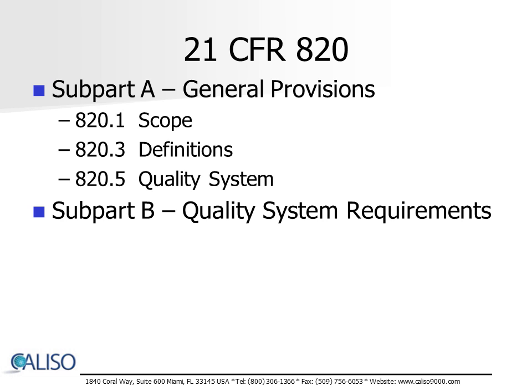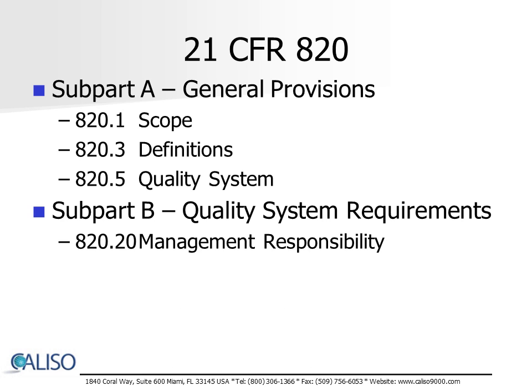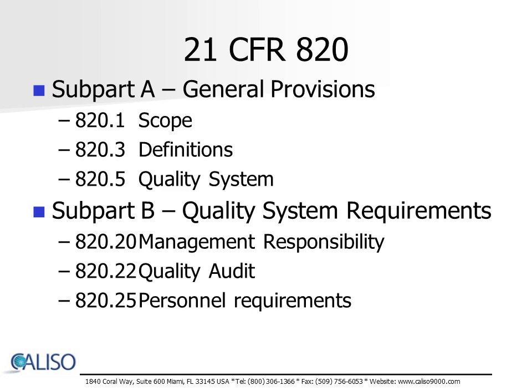Subpart B, Quality System Requirements, which includes management responsibility and quality, such as the requirement for a documented quality management system and management review, quality audits or the requirements for internal audits, and personnel requirements, which includes having competent employees and documenting their training needs.